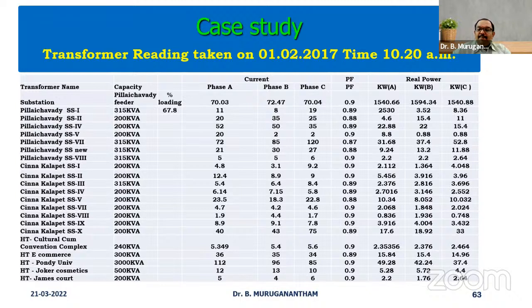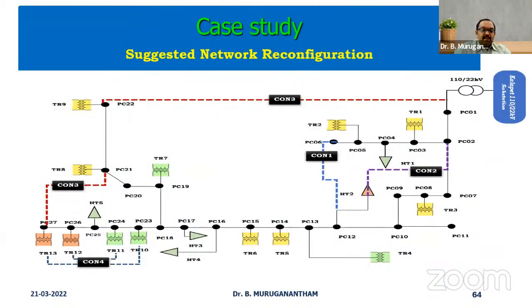So we have run the power flow using GridLab-D, and we found that certain nodes are overloaded. You can see here, transformer 12, transformer 3 is overloaded, and when we went on and completely ran the load flow, we found that 11, 10 and 7 are underloaded. Not even 10% of the transformer was loaded. So you know that when the transformer is underloaded, again, the efficiency gets reduced.